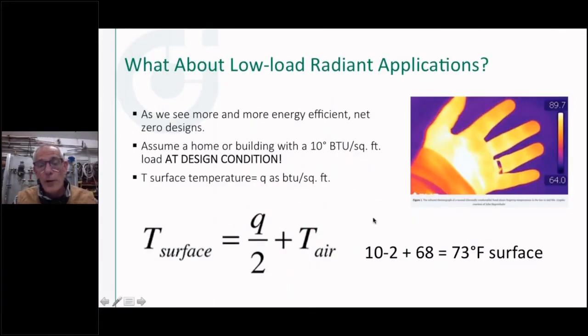So what about low load radiant applications? What we're finding in a lot of the new homes, especially the ones that are trying to get green certified or LEED certified, is they're getting pretty low BTU per square foot heat load numbers. In fact, we've seen some designs with a single digit BTU per square foot requirement on a design day. So how do you get down there? Well, here's what you're going to run into. To put that kind of heat energy into a building in a design condition, you're going to have a pretty low water temperature. And again, right there, 73 degrees surface temperature to get that 10 BTU per square foot load. That's not going to be a warm floor.